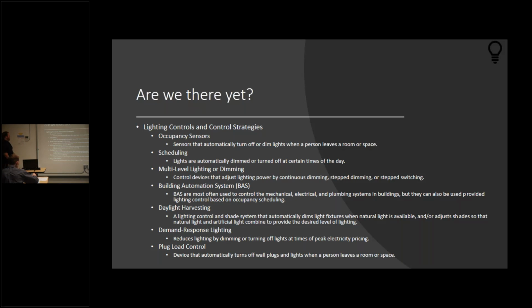And so some of the lighting and control strategies that we see implemented from these standards and increased restrictions and efficiency standards are occupancy sensors, exactly as it sounds. Lights trip a sensor when someone enters a room, and it will either dim or turn off when the last reading is detected. Scheduling, just following a basic schedule. Like between 6:30 and 7:30, all the lights turn off because we know it's unoccupied, no one's working. And then later on around 8:30, the lights will gradually turn on because the cleaning staff, janitorial, other things are coming in to do it, and then it'll turn off again.